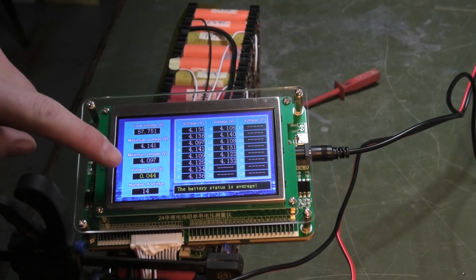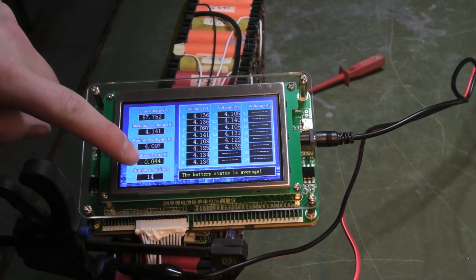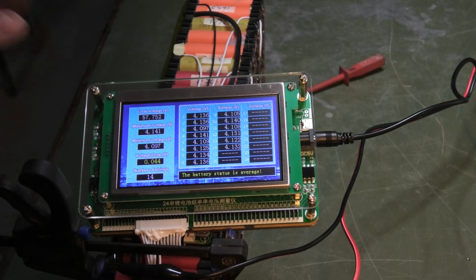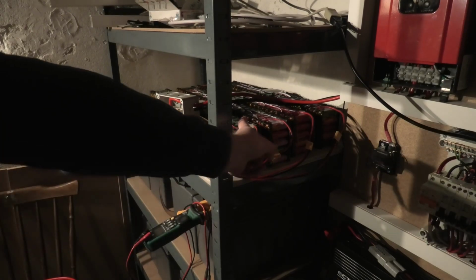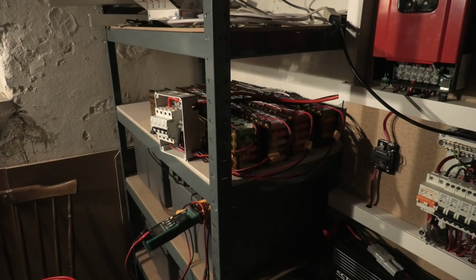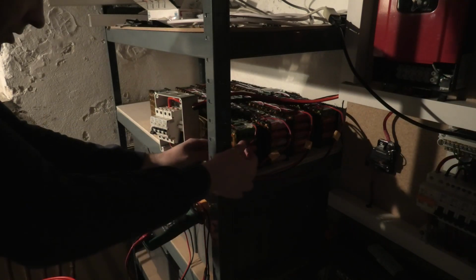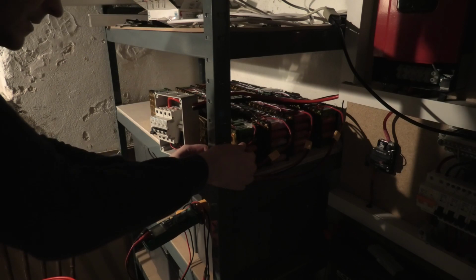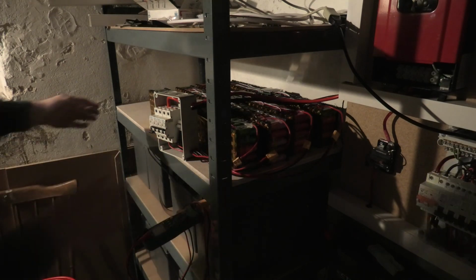Here the whole bank, there is a voltage difference of 44 millivolts, 44 thousandths of a volt. So we're gonna disconnect this and try to swap those 2 batteries around. This is number 1, 2, 3, 4. So the one closest to us is the one that we are disconnecting, and we just disconnect that.